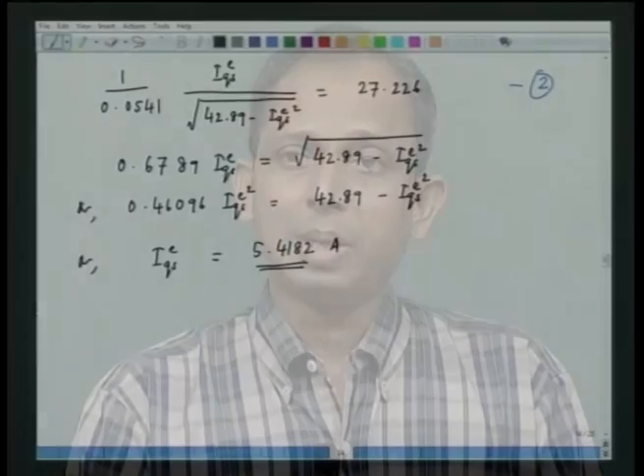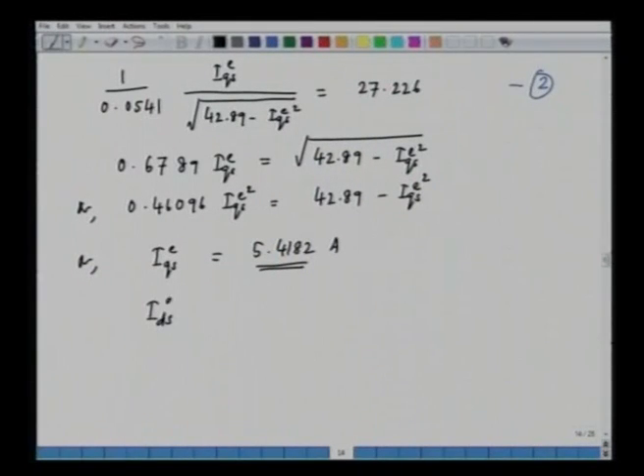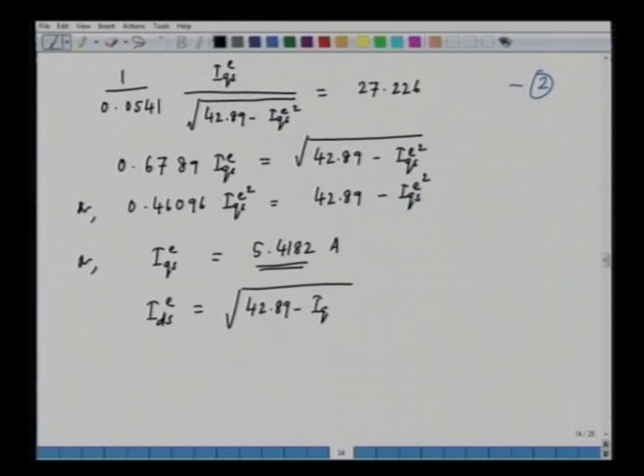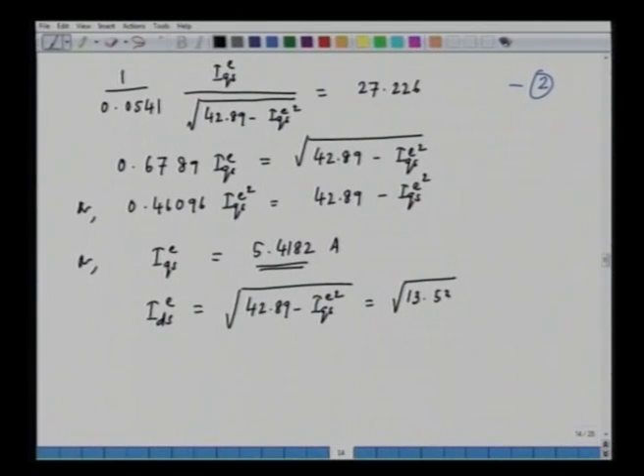We can now also evaluate ids_e. From the first equation: ids_e = sqrt(42.89 - iqs_e²) = sqrt(42.89 - 29.357) = sqrt(13.533) = 3.678 amperes. So the flux component of current ids_e is 3.678 amperes and the torque component iqs_e is 5.4182 amperes.